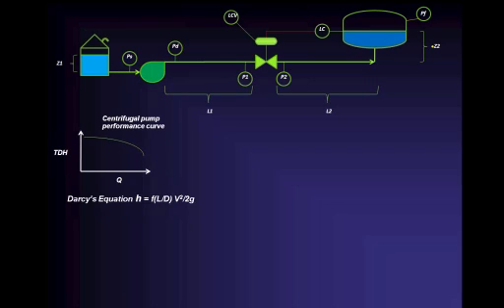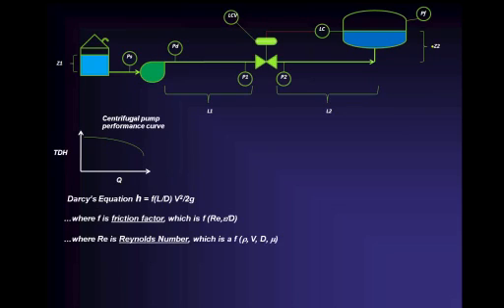It's really nice that H is in feet because it allows us to lay curves on the same graph as long as we're talking about the same units, which is feet in this case. This is a little more complicated because F, the friction factor, is a function of the Reynolds number and the relative roughness ratio of the pipe surface in the interior of the pipe.